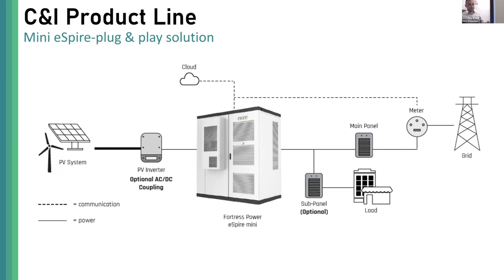And so the eSpire Mini is our new product. Our more established brother product to the eSpire Mini is the eSpire. This is our full-scale C&I ESS solution. The eSpire ranges on the battery side from 280 kilowatt hours up to 4 megawatt hours. Then on the inverter side, it's 125 kilowatts, and you can have up to 5 units for 625 kilowatts of inverter. This one is custom built for project specifications, so allow a 4 to 5 month lead time for the eSpire unit if you're going to be using this for a project. Something to keep in mind. I think compared to a lot of commercial manufacturers, 4 to 5 months is a pretty short lead time, so that should meet the demands of most commercial applications since they move a lot slower than the residential side does.